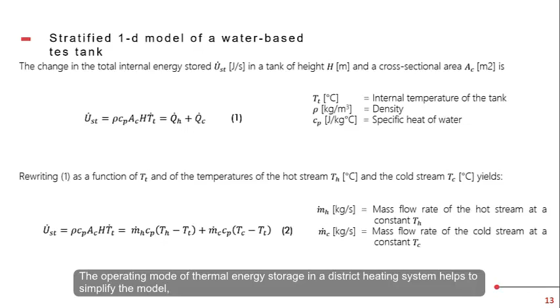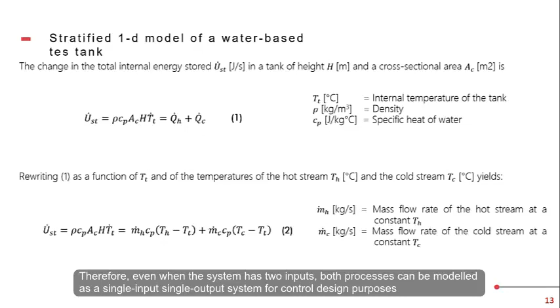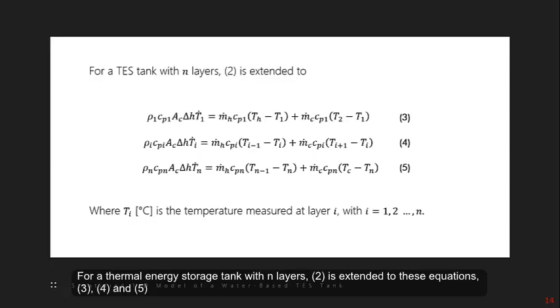The operating mode of thermal energy storage in a district heating system helps to simplify the model, as the charging and discharging processes are not carried out simultaneously. Therefore, even when the system has 2 inputs, both processes can be modeled as a single input, single output system for control design purposes. For a thermal energy storage tank with n layers, equation 2 is extended to these equations 3, 4, and 5. It is assumed that the tank is fully charged when the temperature in all layers is 90 degrees Celsius, and conversely, fully discharged when the temperature in all layers is 60 degrees Celsius.